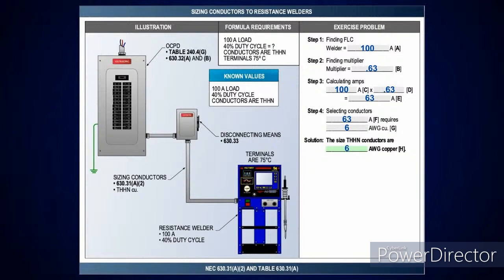Okay. And then this is the same thing. I've got a 100 amp resistance welder, 40% duty cycle. I'm going to go over and look at sizing the conductors at 630.31(A)(2). And you're going to see in step 1, the welder's good for 100 amps. For my 40% duty cycle, I find my multiplier, which is 0.63. Take the 100 amps times 0.63 gives you 63 amps. And then like the last problem, table 310.16, in the 75 degree C column is 65 amps, which would be a number 6 copper conductor.